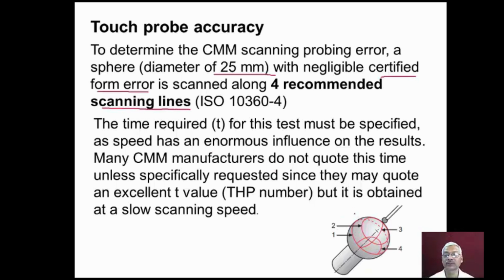So in this picture you can see this is the master ball, which is used to calibrate the probes selected. So this is the probe that is selected and which is to be calibrated. The master ball is placed at the specified location on the CMM table, and the probe selected is made to scan the surface of the master ball along the 4 lines. This is line number 1, line number 2, line number 3, and we have line number 4.